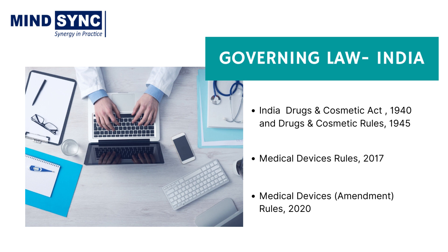The Indian government decided to simplify the medical device registration procedure by enacting the Medical Devices Rules, 2017, which have been monitored by the CDSCO. On April 1, 2020, the Medical Devices Rules has been revised as Medical Devices Amendment Rules, 2020, and will apply to all newly notified medical devices.